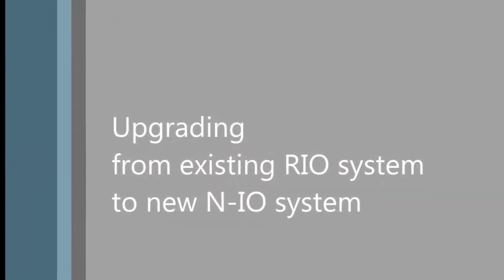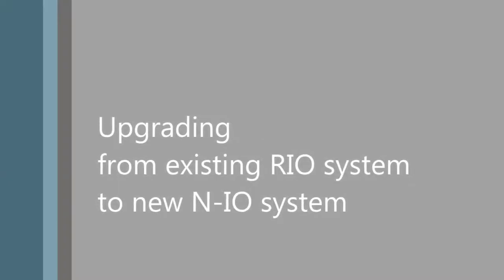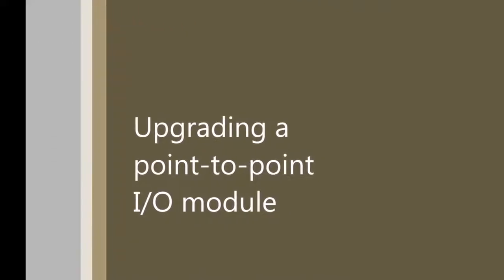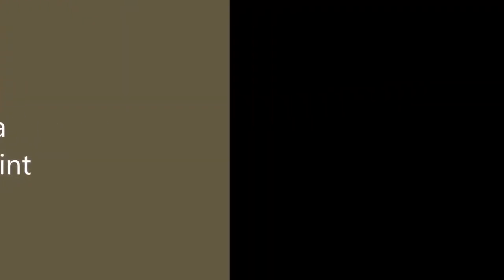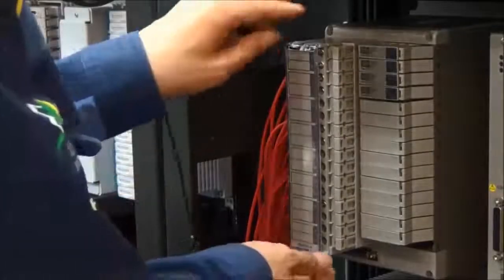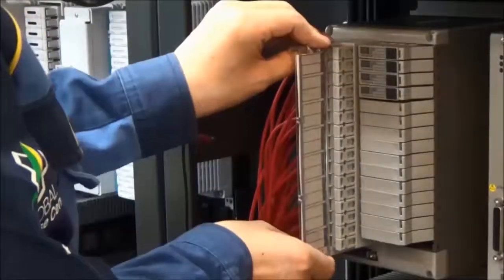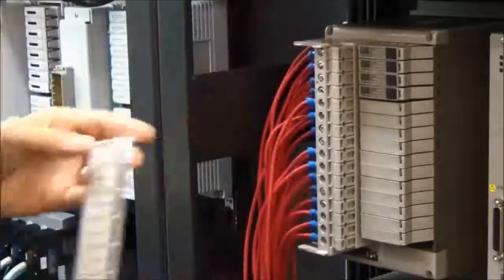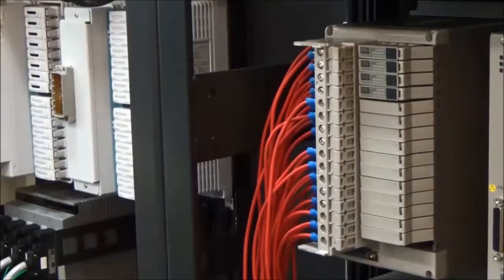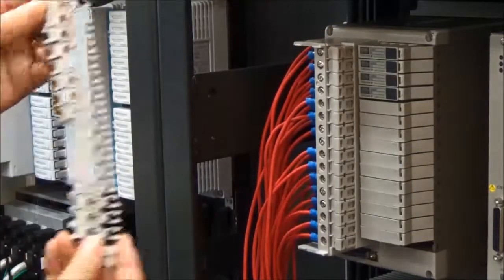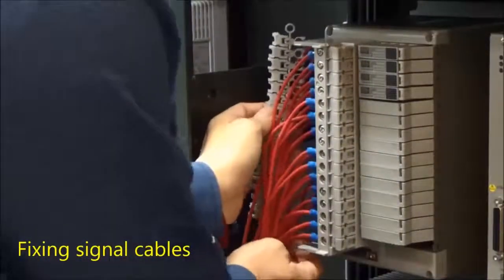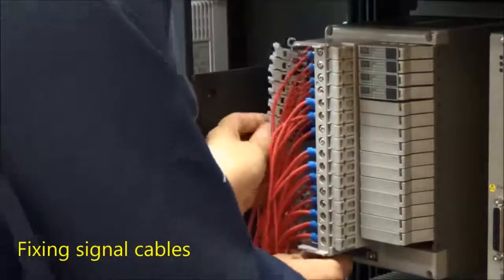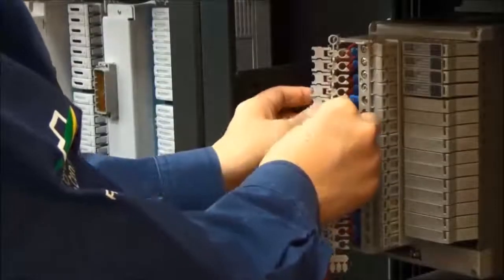Now, we present you an overview of how to replace I/O modules. A point-to-point module requires the field wires to be disconnected before proceeding. To prevent wrong connections, fix the field wires using a field wire fixing tool first, and reconnect field wires.